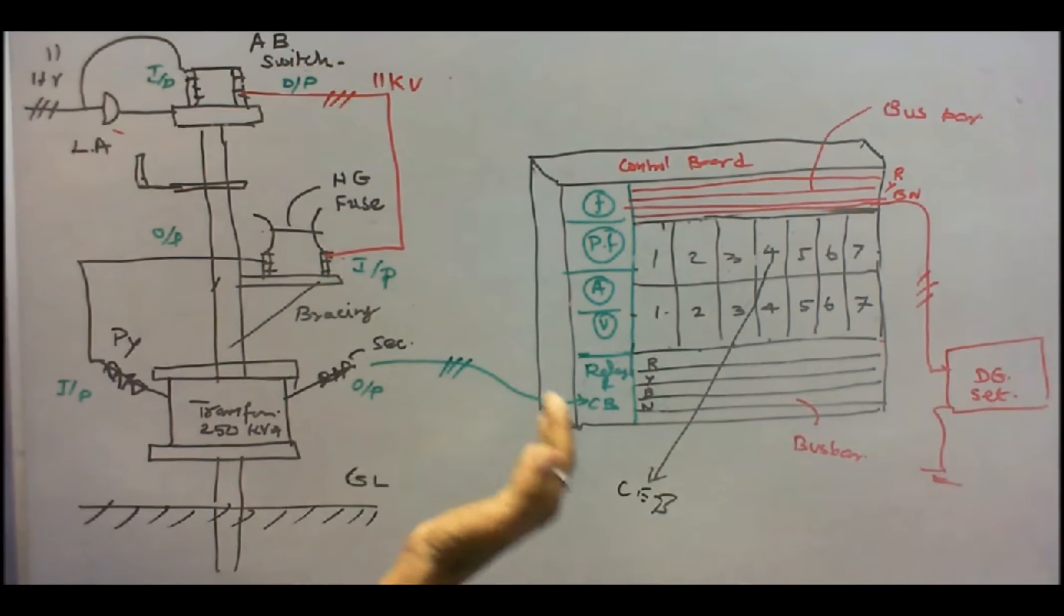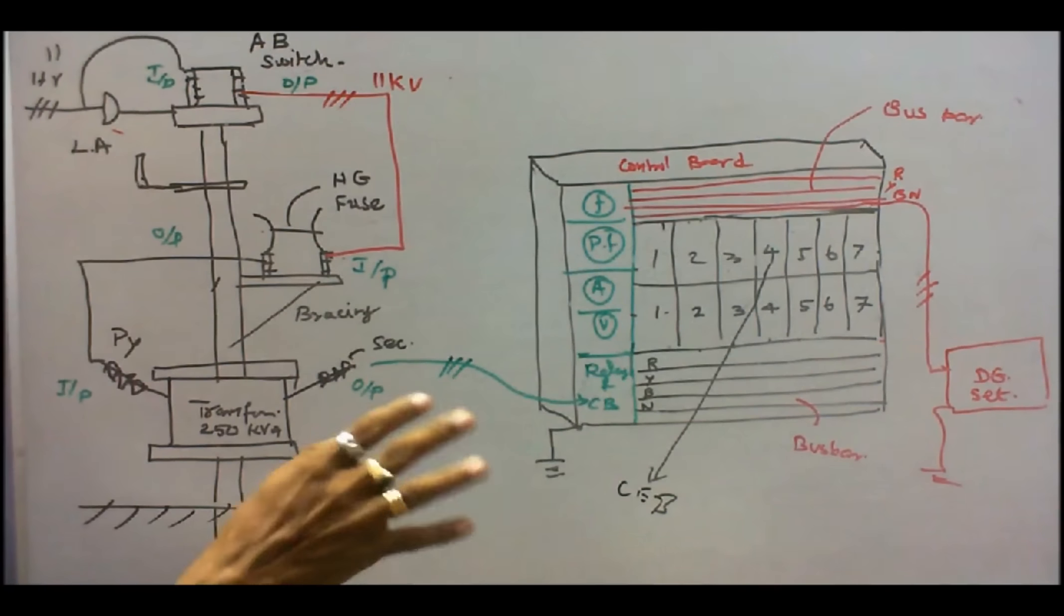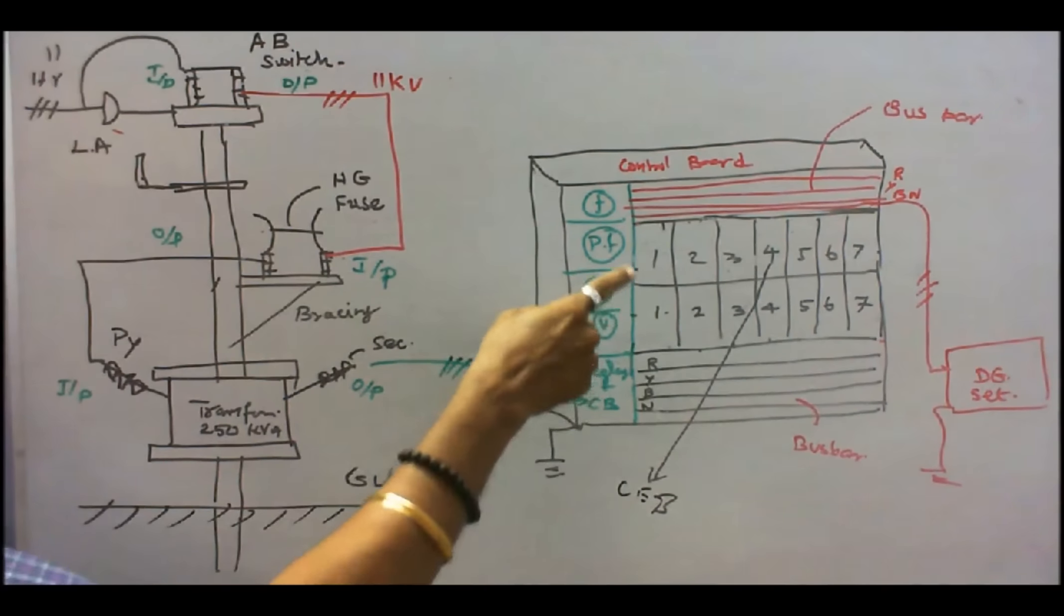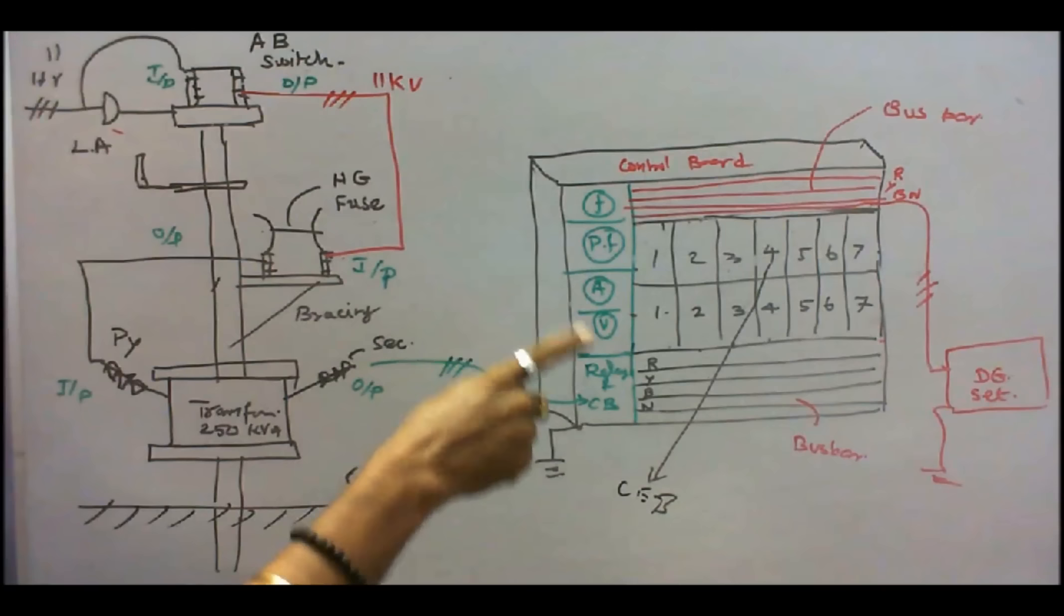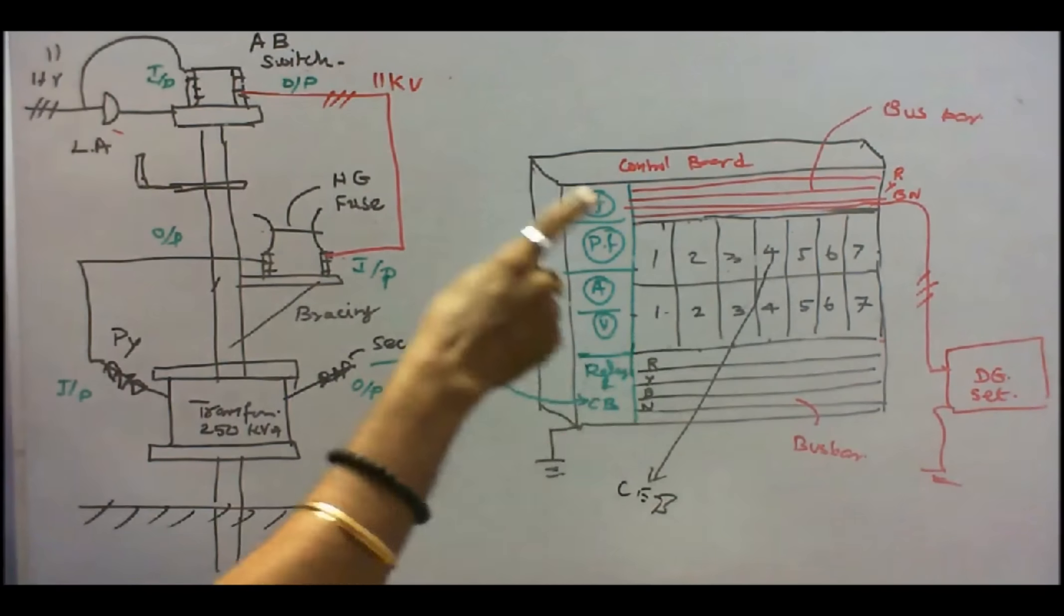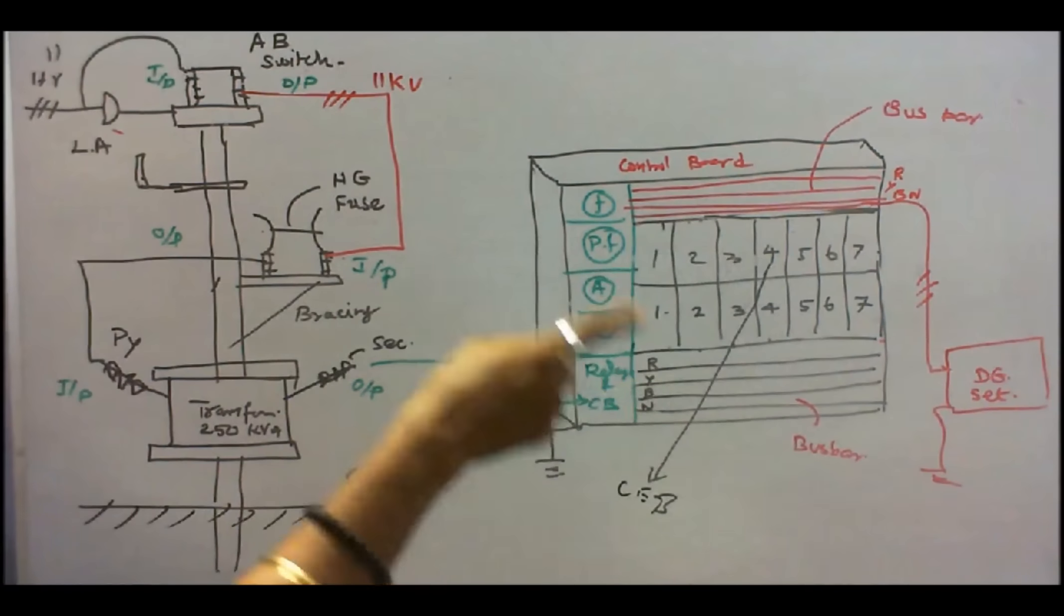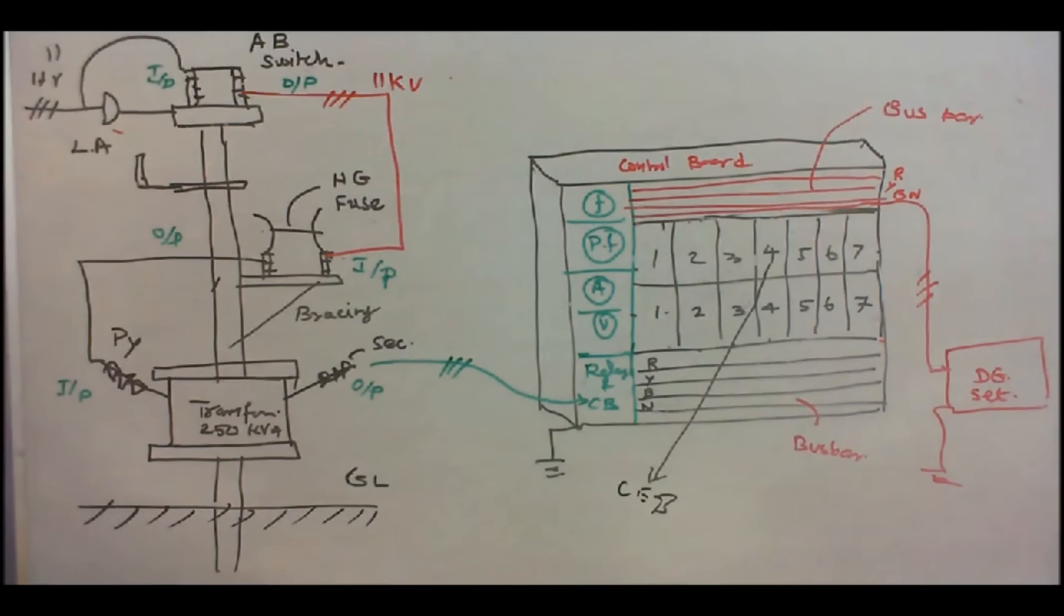Suppose I want to operate some part of the load on TNEB supply and some part on the DG set. What I have to do? These switches are interlinked. That is a very interesting thing. I can't operate the switch at the same time. Suppose I want to operate switch 4, I must switch off the switch 4 then only I can switch on. Such a way that it has been designed. So from the switch output goes to the civil engineering block.